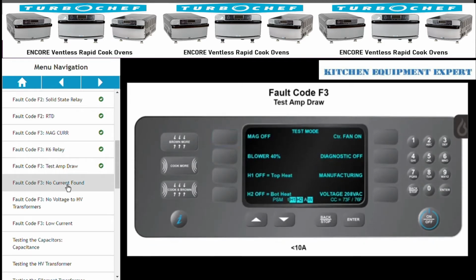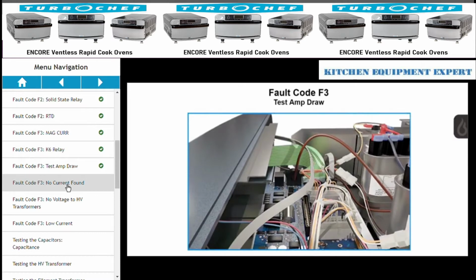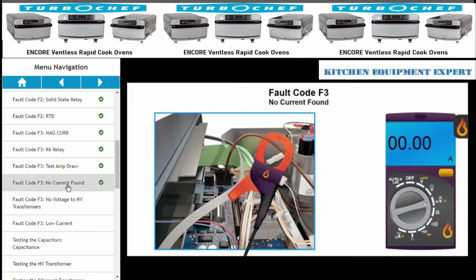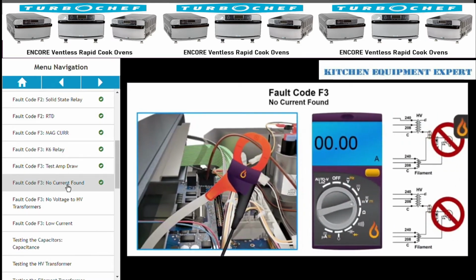If you see less than the normal operating current based on 208 or 240 voltage, you have a problem. Once the board has sensed 10 or more amps on the brown wire, the backlight behind the W at the bottom of the screen in test mode will go out. If you are pulling more than 10A and the W is not on backlighting, the control board will need to be replaced. If you're not seeing any amperage, it indicates that neither microwave circuit is getting voltage.